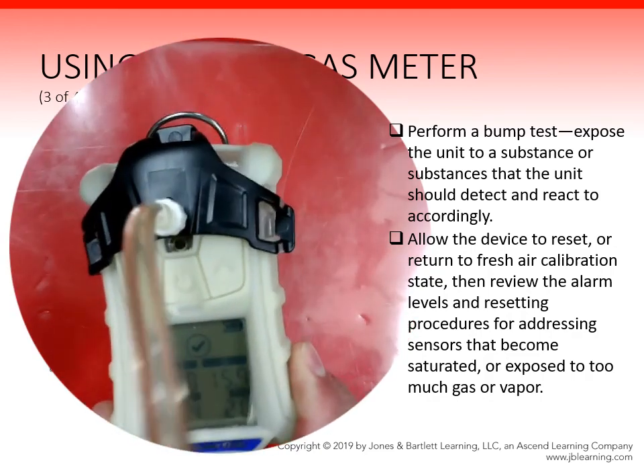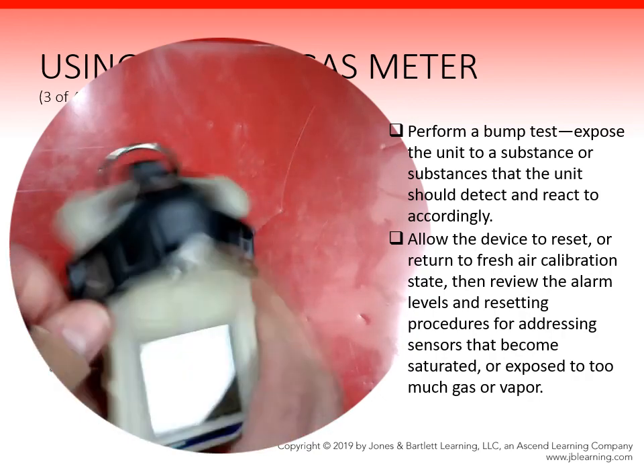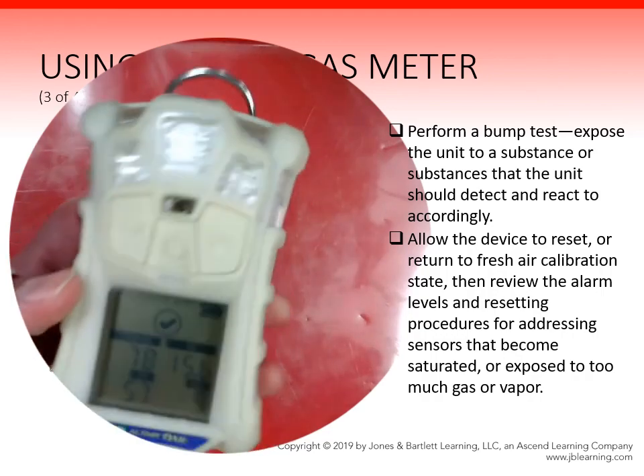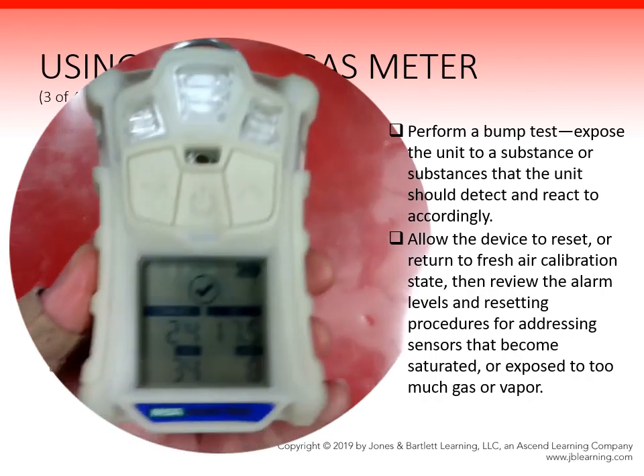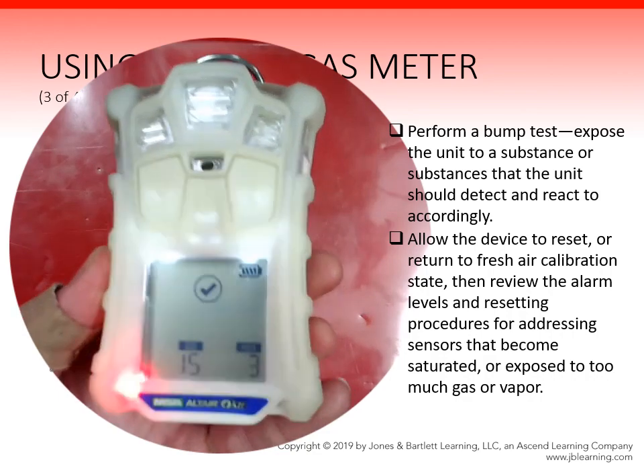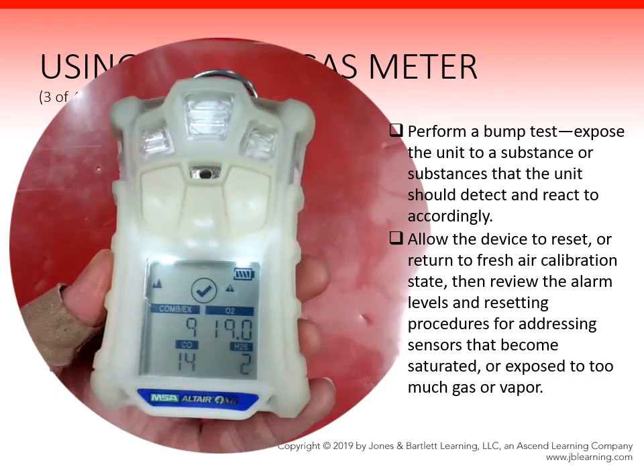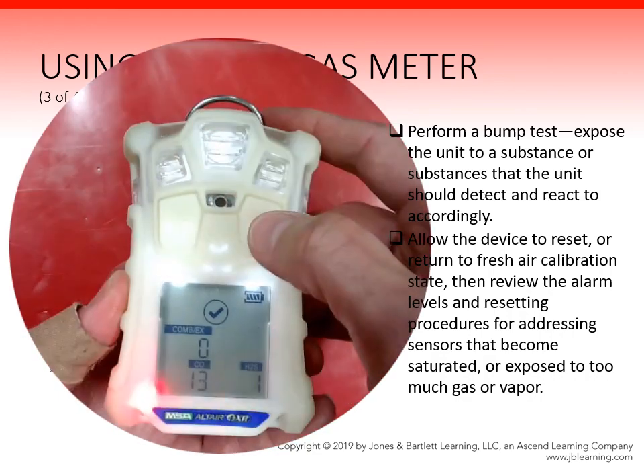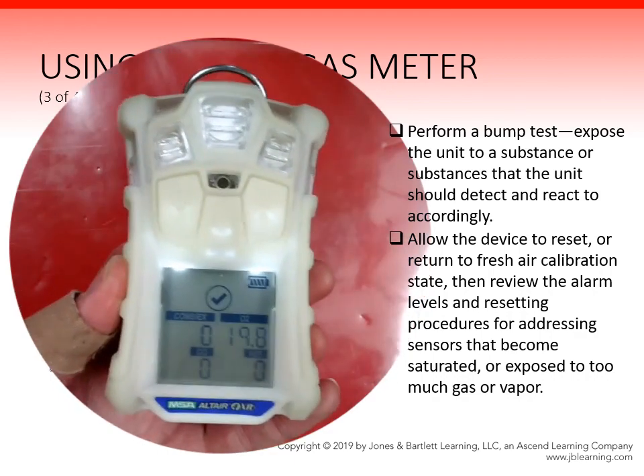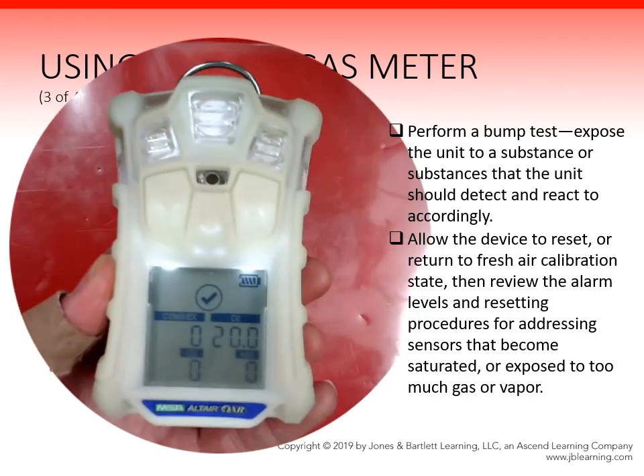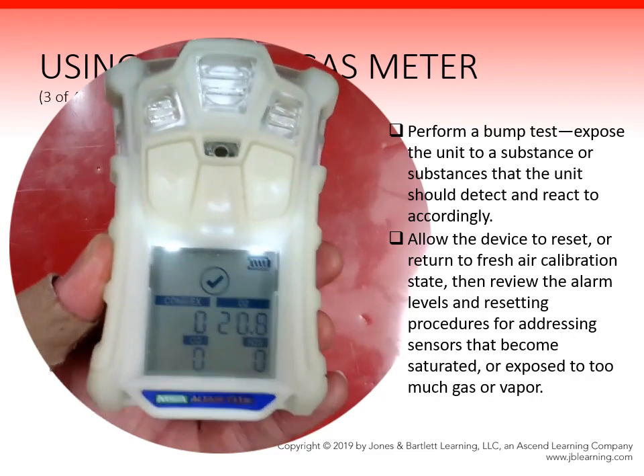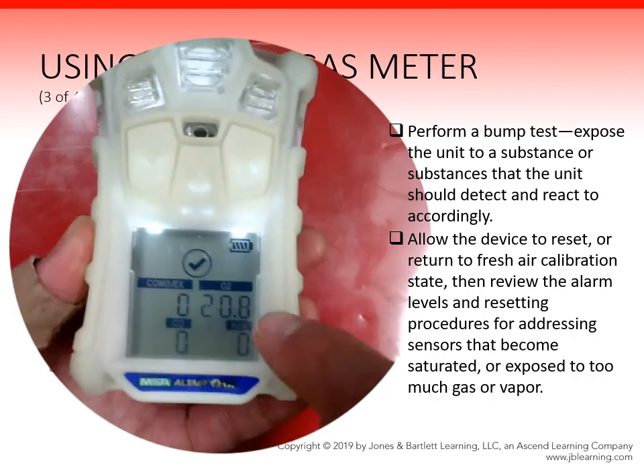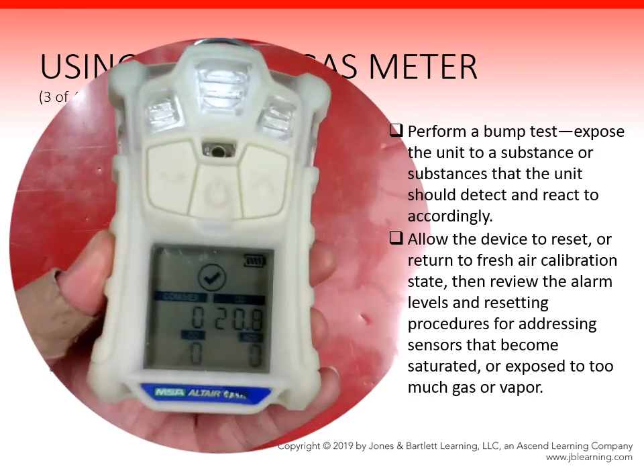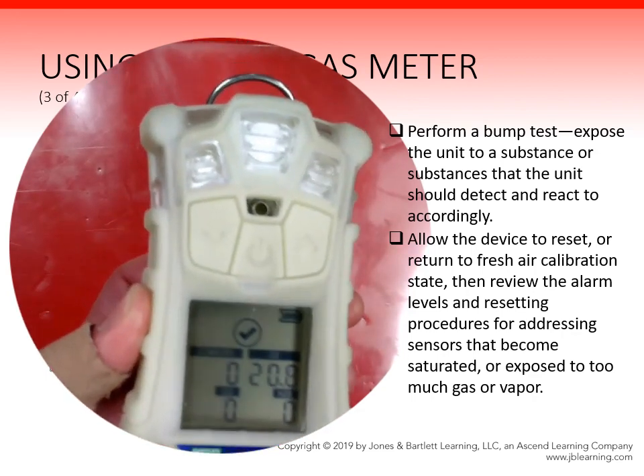Once the bump test is complete, I'm going to turn the gas off and remove the harness. You'll also hear this start to make alarms because once it's done with the bump test, it takes a little bit for those sensors to clear out, and you'll hear an alarm. You can clear that alarm out by hitting the up arrow key, which resets those alarms. Once the other sensors are zeroed out and the O2 has climbed up to 20.8, we're done. That bump test is complete.